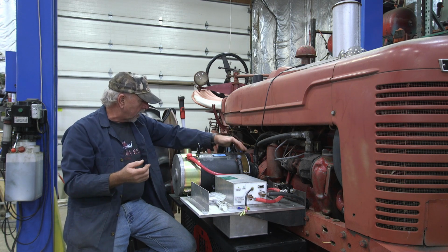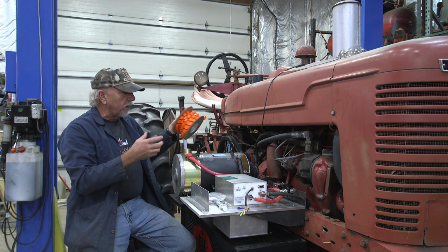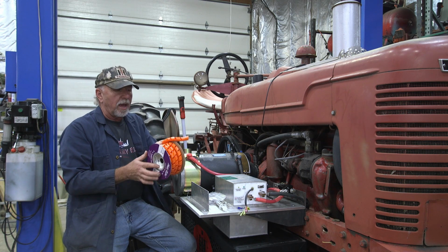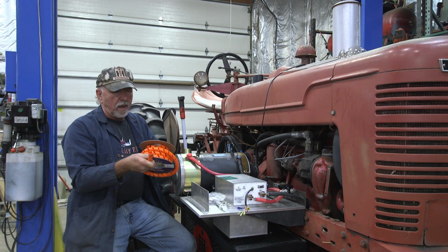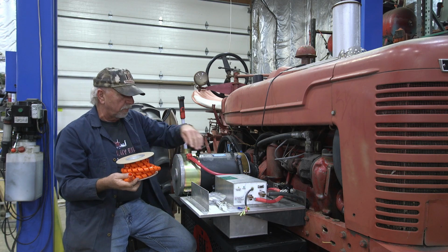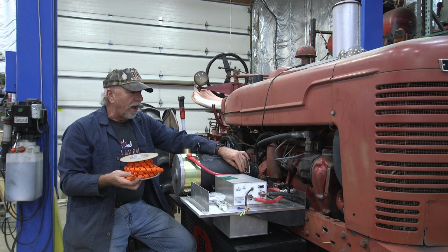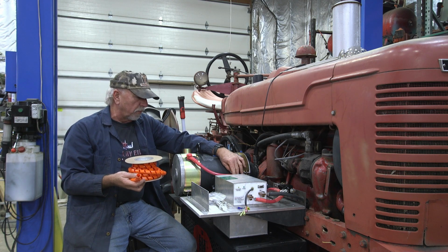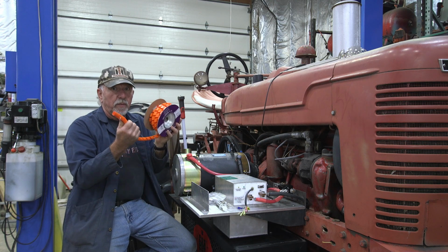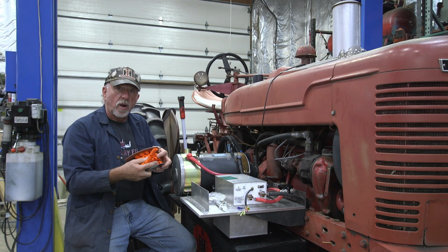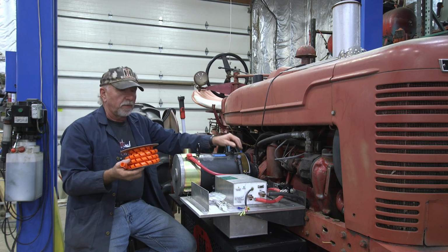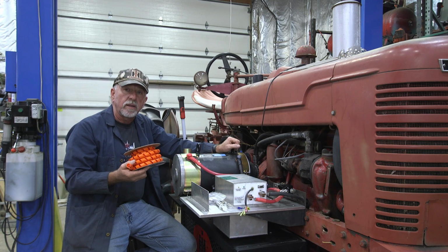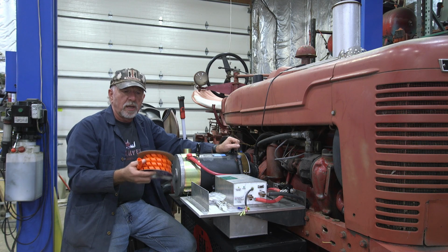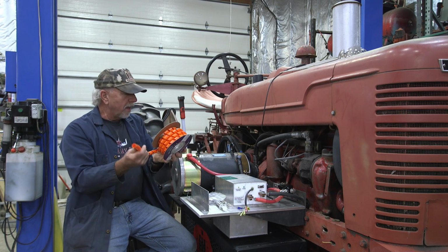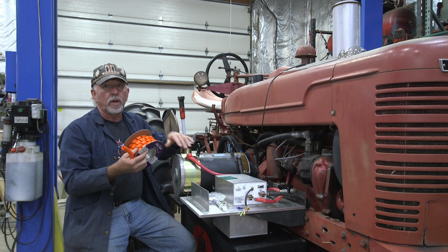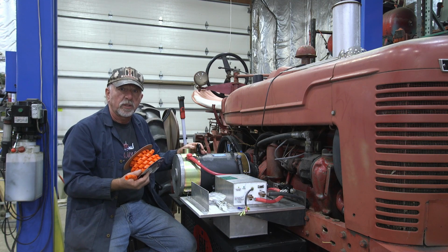Last but not least, and it hasn't been done yet, for any cables that will be exposed, we'll add an orange wrap indicating they are high voltage - not simply black and orange, or black and red, without this on there, because this is one of the requirements for high voltage. Anything above 60 volts, the rule is that we need to mark them as high voltage, so we'll put this wrap on all the exposed cables to inform everybody this is a high voltage environment.